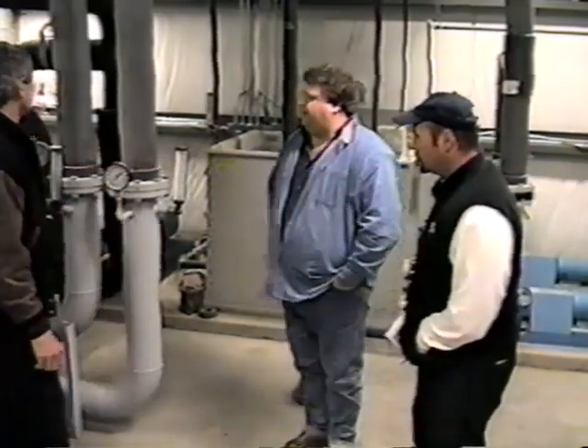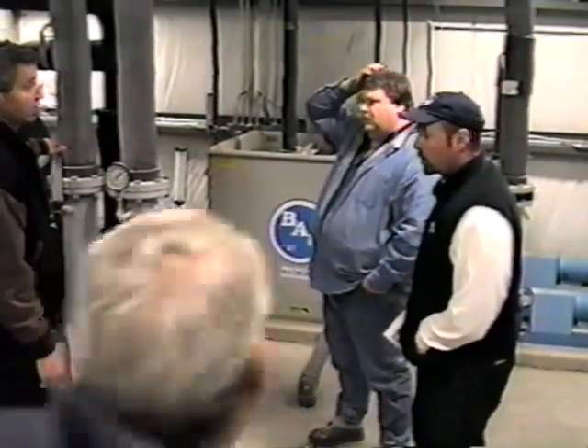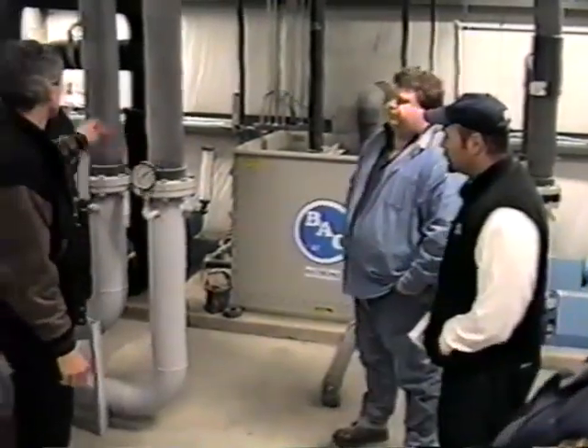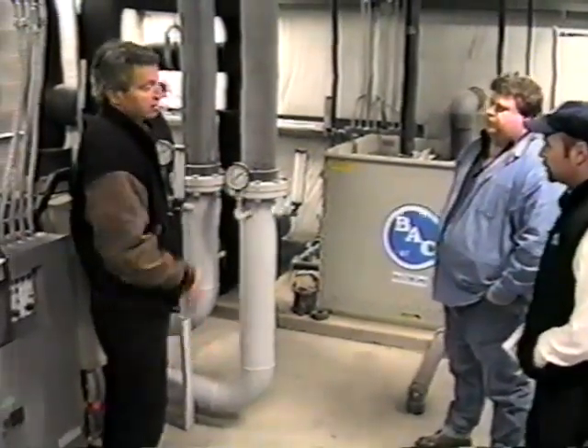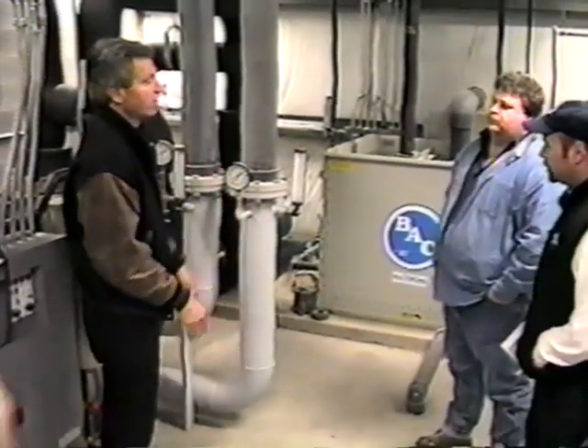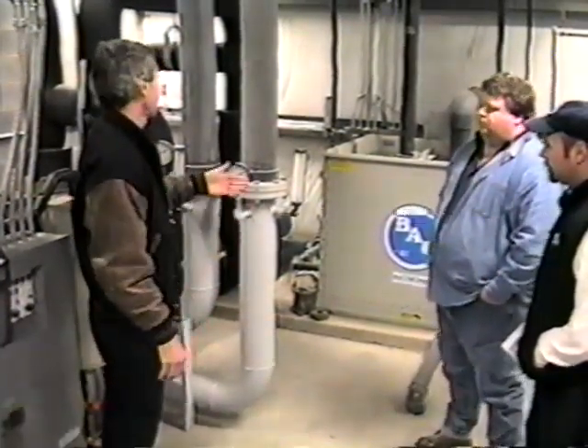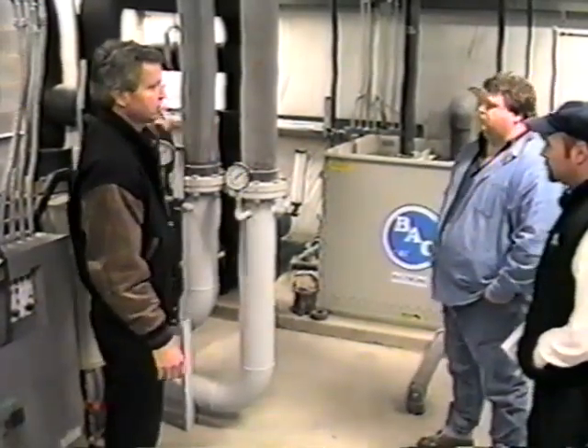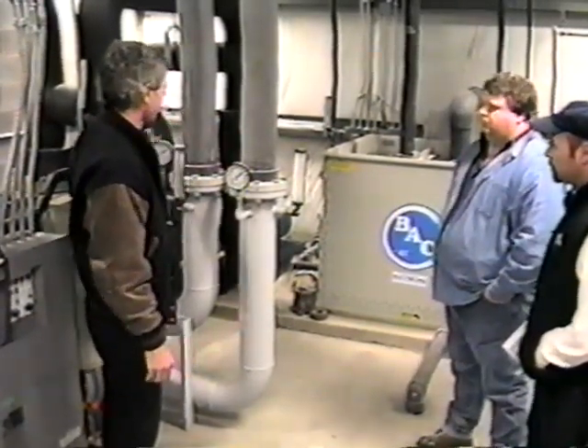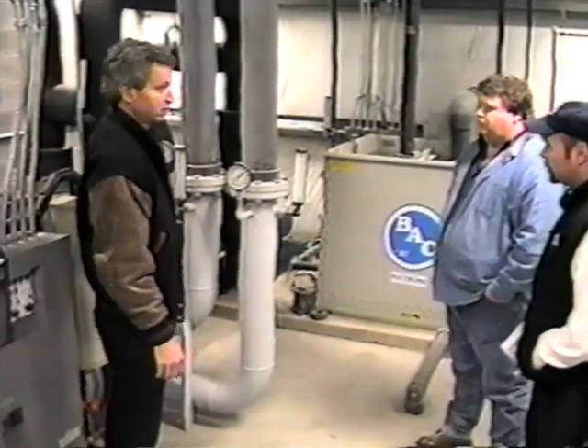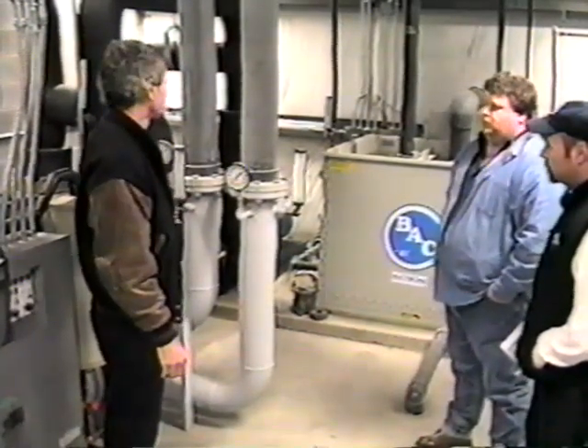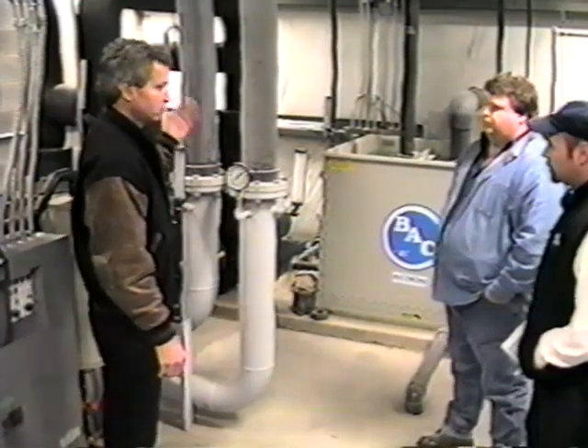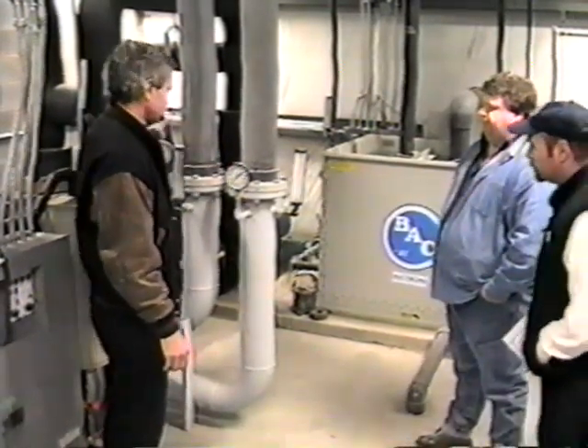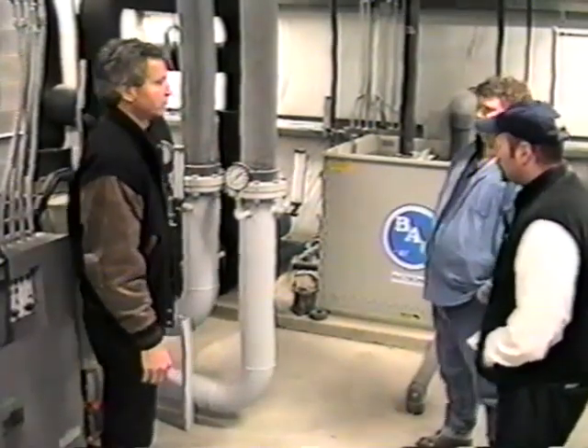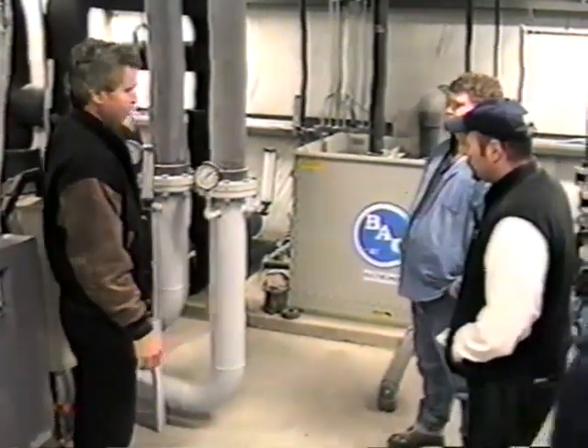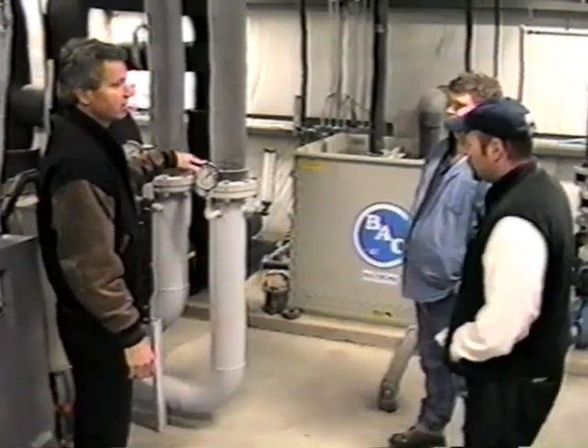The other thing you might want to log is your condenser water temperature, as well as your pressures and your gauges, because that's an indication of whether your flow is going up or down. It'll be a good reference to refer back to the normal pressure differential. As this pressure differential goes up, essentially barring a plugged condenser tube section, your flow is going up. As it goes down, your flow is going down. With a plugged condenser, that difference is going to be higher, but the inlet is probably going to be higher as well.